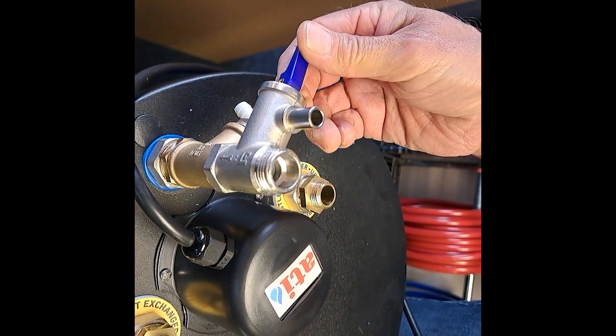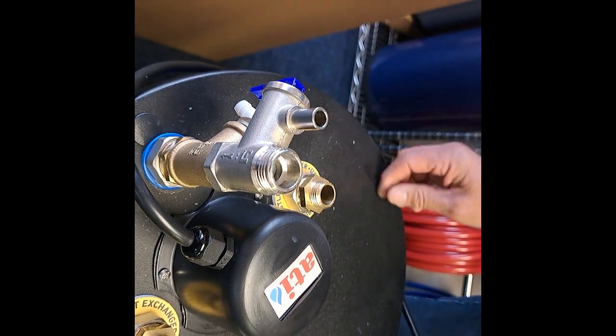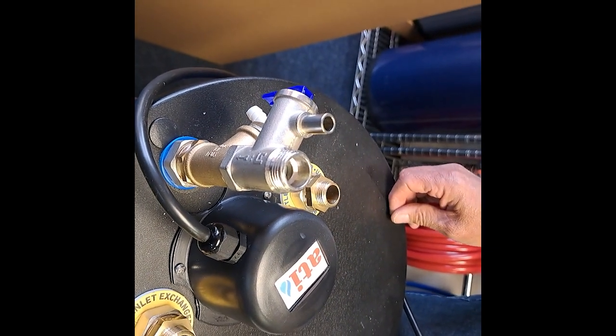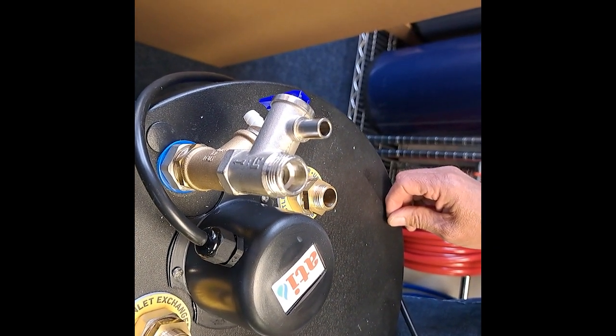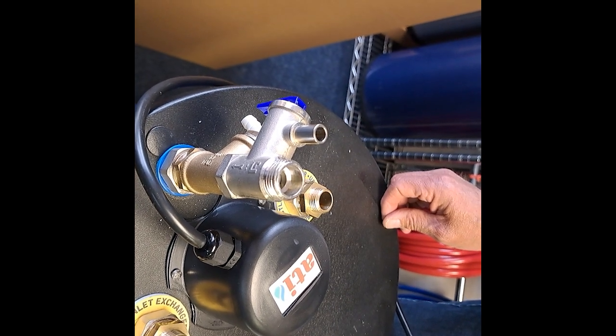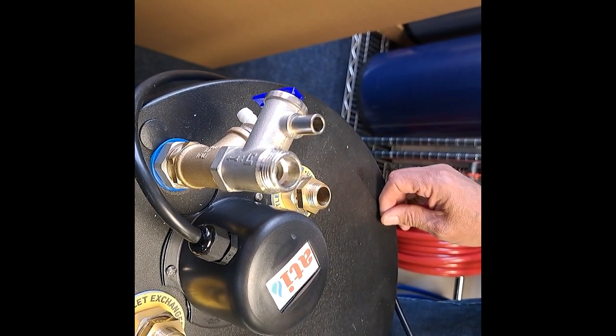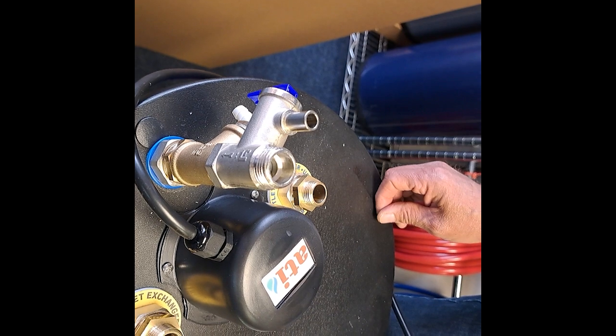If it doesn't work, it may be that your expansion tank or your accumulator has lost pressure. It should be around 1.5 bar. If there is little or no pressure, then the bladder inside or maybe the complete accumulator need to be replaced.